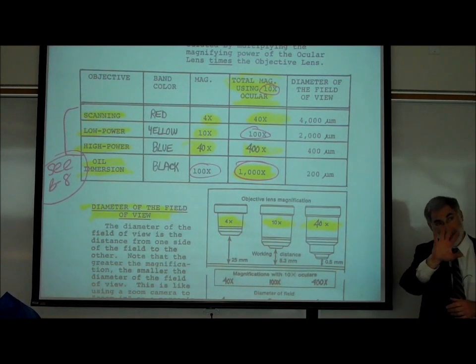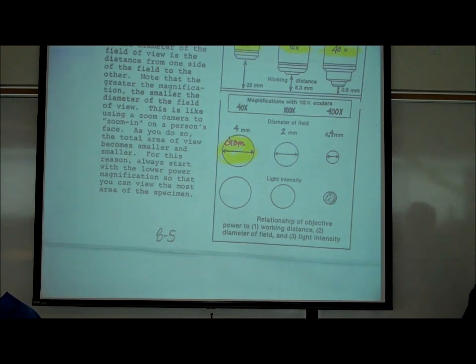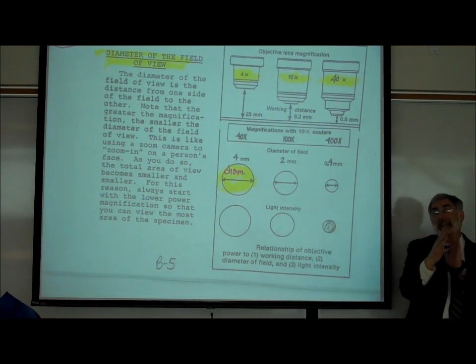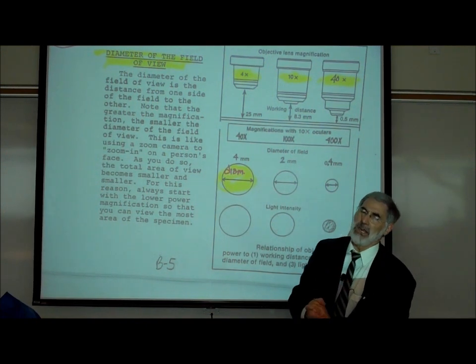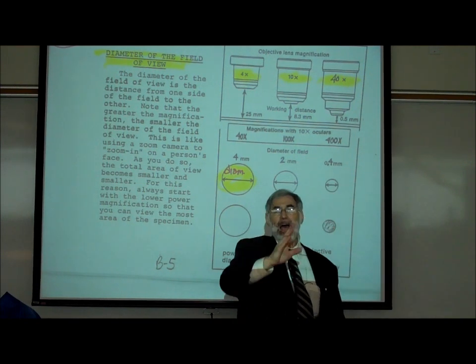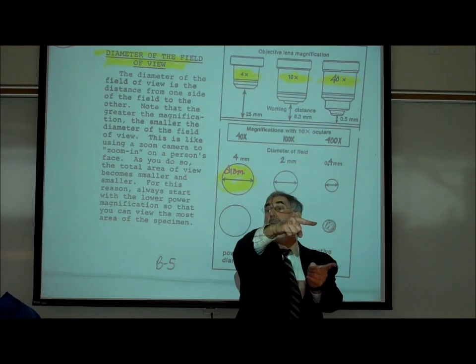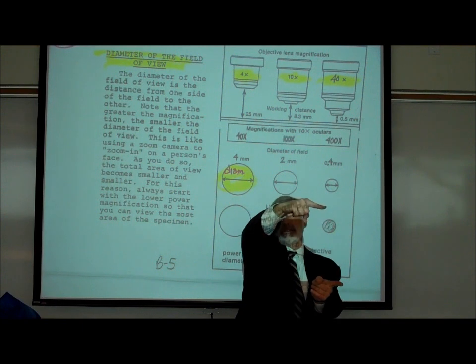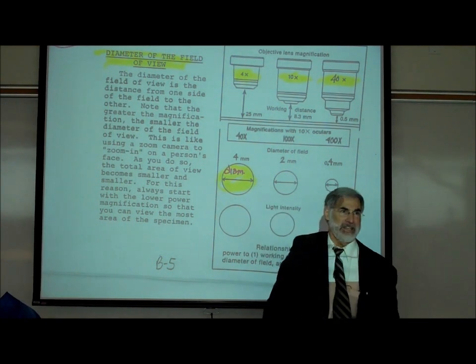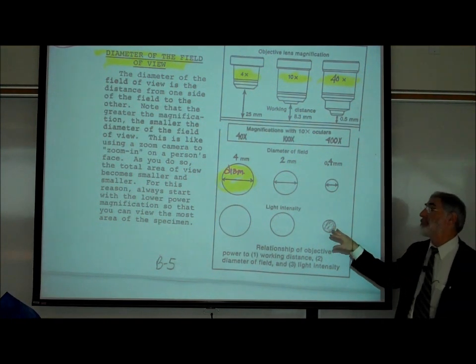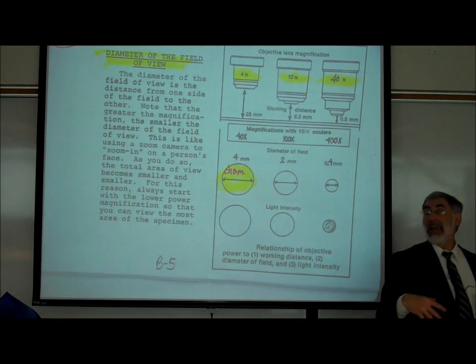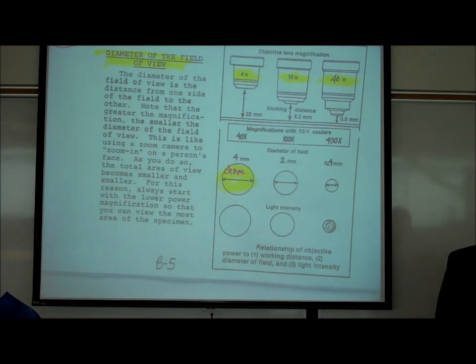You're going to have to use these numbers, so that's why all this is important. Also note: as you increase the magnification, the image generally gets dimmer, because the higher magnification objective lenses are longer and contain more lenses inside. The more light has to travel through lenses, the dimmer it gets, so sometimes you need to increase the light at higher magnification.